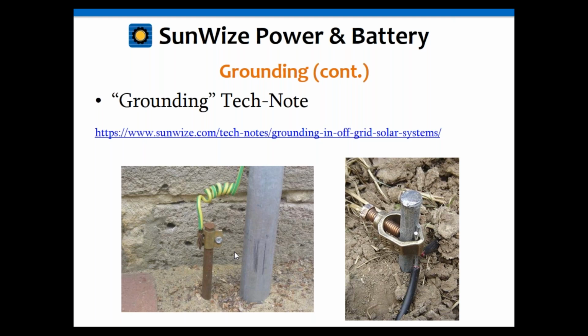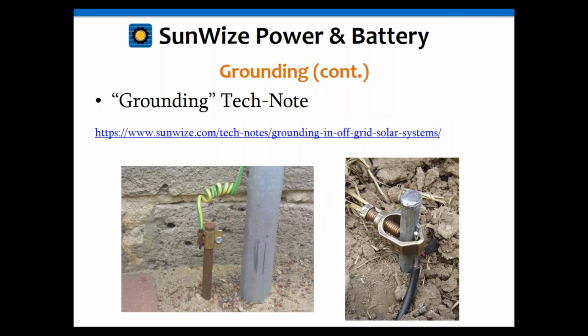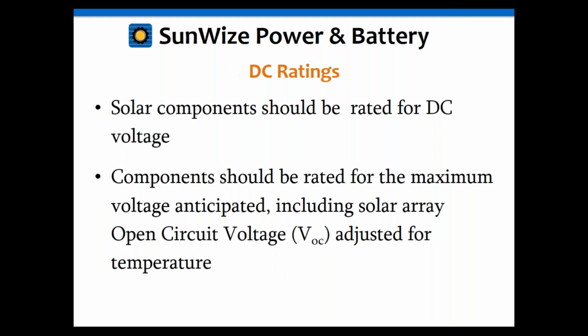Oh, by the way, you should keep your ground separate. You should keep your electrical ground and your mechanical ground separate until you get to the ground rod or the ground system. At that point, you can combine them together. You don't need a separate ground rod for the electrical ground versus the mechanical ground. You can combine them over at the ground rod. The reason to keep them separate except for one point is to prevent a ground loop. So if you can bring them to one point, then that's fine. Then you can run that wire from there. But again, you only want one ground for that.